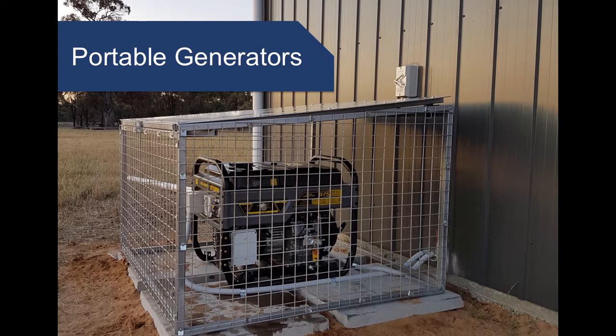bit of battery storage. And we noticed the voltage on one of the phases was quite high to start with, no solar there. And even though it wasn't causing a problem, we thought, well, let's get onto this before it does. Contacted Powercor, said we think there's a problem here with high voltage. They were out within the week, tapped the transformer down, and solved that issue. So they're pretty responsive to this sort of stuff.